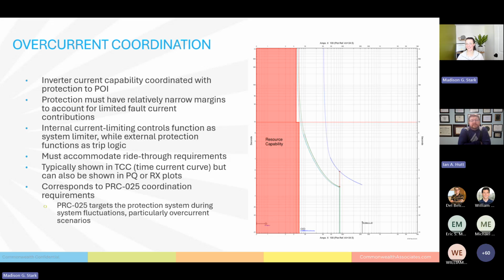That answers your question. A couple of good things to mention here too: this is a log scale curve. So it looks like we're kind of tight around where that red horizontal line is, but mind you, that's in the seconds range, so there is a lot of margin there. Once we get down towards the bottom of the curve, we're talking cycles. It's much faster. But Madison's absolutely correct that we try to make sure there's margin between our protected devices. There's art and science here too. There are trade-offs that sometimes must be exercised, but in general, assuming we have, say, a 3-cycle breaker, we want to account for relay operating time, lockout time, breaker operating time, and some additional margin to account for unknowns. Things like accuracy and saturation can affect relay operations. We want to make sure we cover those as well to give us the best chance for coordination and success when we're looking at coordination plots.